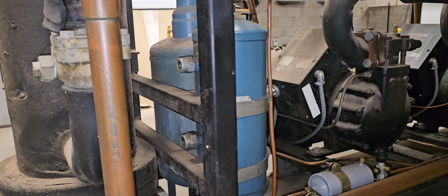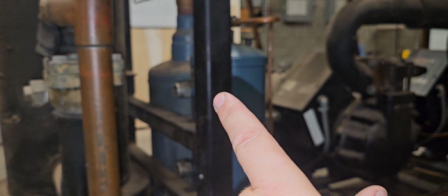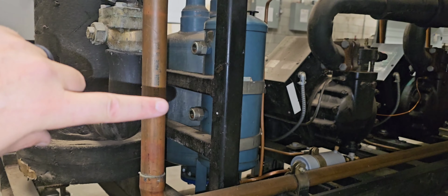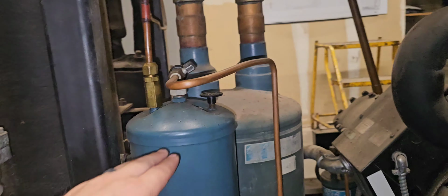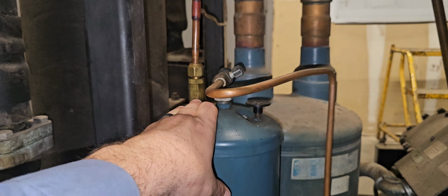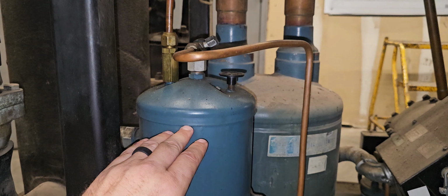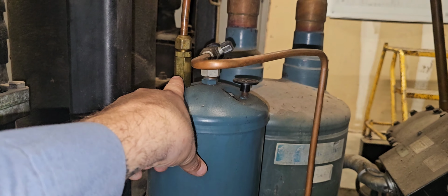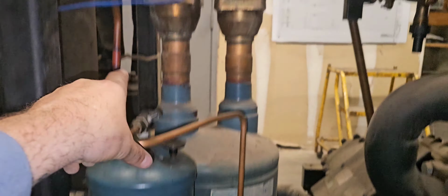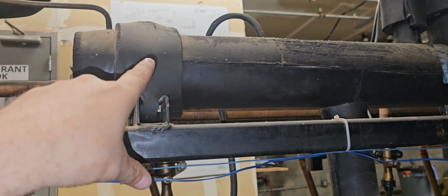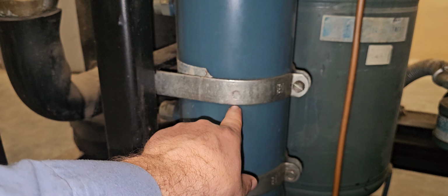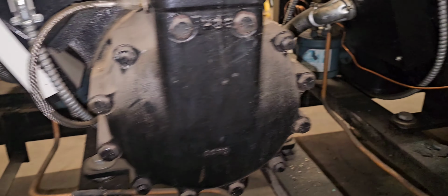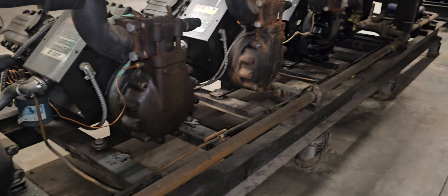And I said in the short, you have your low and your high sight glass. Now, you only want your oil level to be at that low sight glass. The reason being is if you get too high of oil, say we have our oil sitting up in here, we're gonna block that check valve. So one, we're probably not gonna pump out the pressure that we need to, and two, you're gonna start feeding oil from your reservoir just straight back into your suction header. So you only want that ball to be floating at that first sight glass right here. As long as you have that first sight glass floating, you're gonna be good. So that's pretty much it.